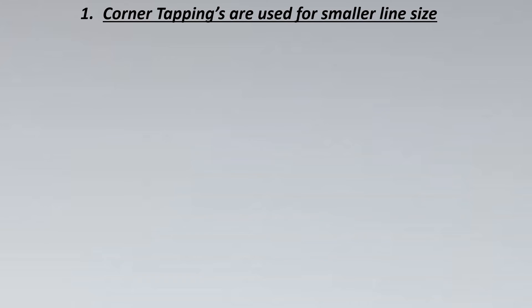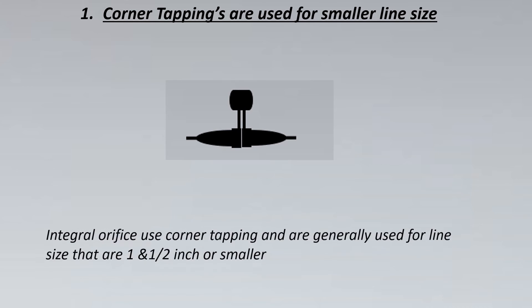Corner tappings are usually used for smaller sizes because the vena contracta would come at a smaller distance from the DP created. Hence we can measure it very close to the orifice or the DP meter. So in corner tappings, especially a meter called an integral orifice meter is used. As a thumb rule, for line sizes that are one and a half inch or smaller, we usually go for such integral orifice assemblies.